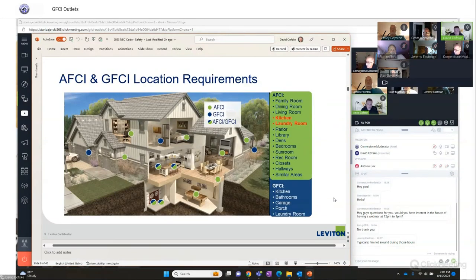Now we get into, okay, in a home, where do I use GFCIs and where do I use AFCIs? Basically the code says today, AFCIs are the top green section, the right top green section. In all those rooms, they need to be protected by AFCI under the code. And the bottom right, the blue section, those areas need to have GFCI protection. When you slide up and you see the kitchen and laundry room highlighted in red, those areas in a home need to be AFCI and GFCI protected. So kitchens and laundry rooms need to have both AFCI and GFCI protection by the code.